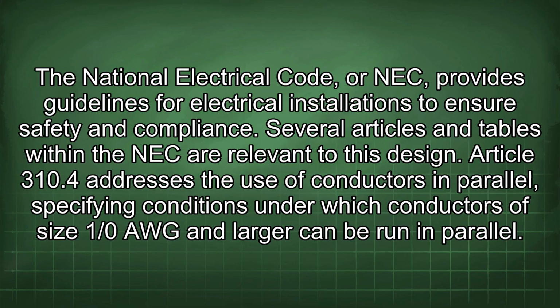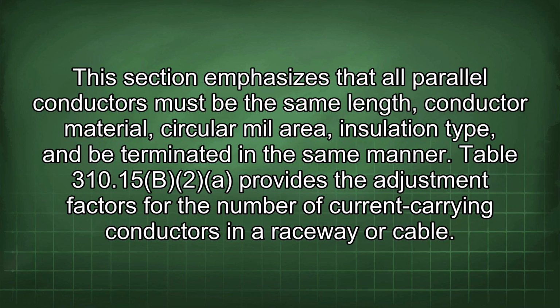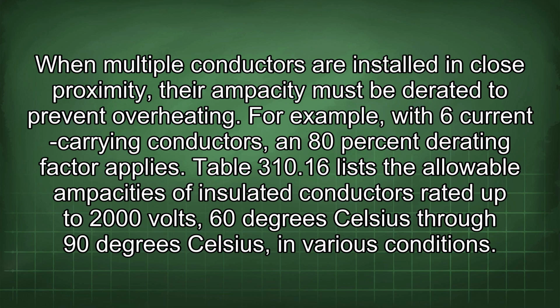The National Electrical Code, or NEC, provides guidelines for electrical installations to ensure safety and compliance. Several articles and tables within the NEC are relevant to this design. Article 310.4 addresses the use of conductors in parallel, specifying conditions under which conductors of size 1/0 AWG and larger can be run in parallel. This section emphasizes that all parallel conductors must be the same length, conductor material, circular mil area, insulation type, and be terminated in the same manner. Table 310.15(B)(2)(a) provides the adjustment factors for the number of current-carrying conductors in a raceway or cable. When multiple conductors are installed in close proximity, their ampacity must be derated to prevent overheating. For example, with 6 current-carrying conductors, an 80% derating factor applies.